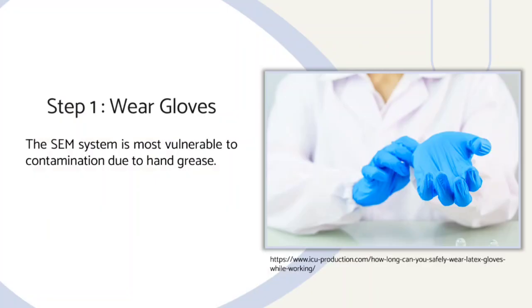Step 1: Wear gloves. Do not use your bare hands to handle any sample components, including samples, sample holders, sample stubs, and the sample exchange equipment. The SEM system is most vulnerable to contamination due to hand grease.